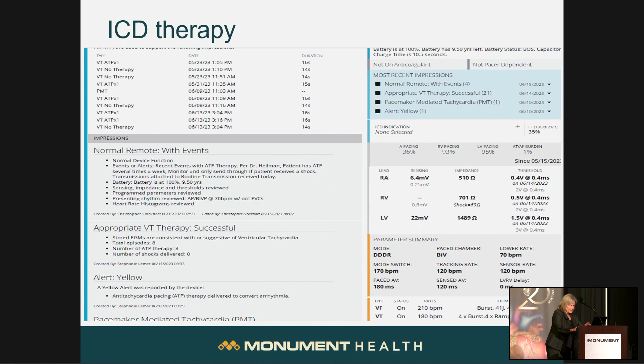and it's apparently programmed so that after 14 seconds, then it would start delivering ATP, because you'll see no therapy programmed or no therapy delivered. When it gets up to 15 seconds, 16 seconds, then you'll see the ATP on this, the way this is set up. And then this is his arrhythmia logbook. So you can see in March he had a few episodes and terminated with ATP. And then in April he started having more and more VT episodes, VF episodes, and got more ATP.